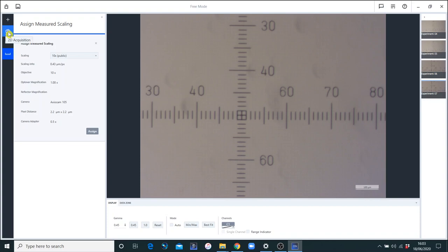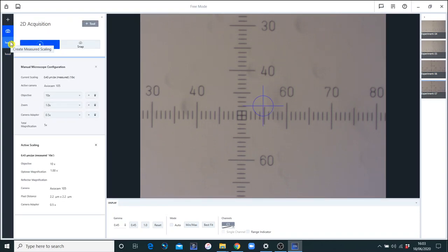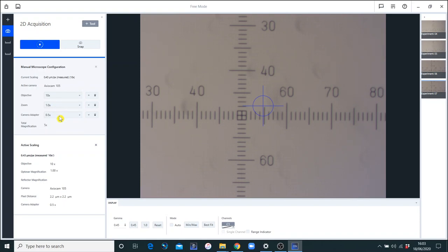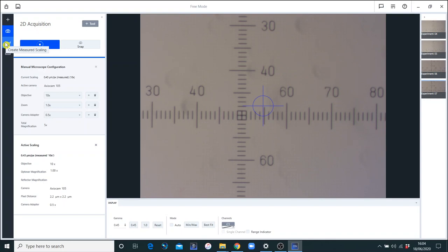Okay, so to recap, what we would do to create a scale is we edit this list, the manual microscope configuration. Out of the box, there'll be lots of options in the dropdown. We just select the objectives we're using, zoom on one, C-mount adapter on 0.5. We snap the image. We then draw a line to the line length measured from the stage micrometer. And the trick, as you remember, is to call it the same name as what we're using here, so 10x.